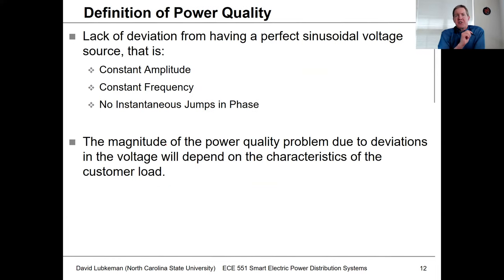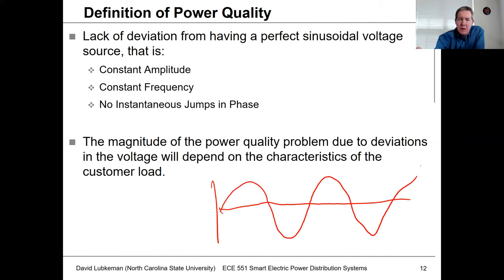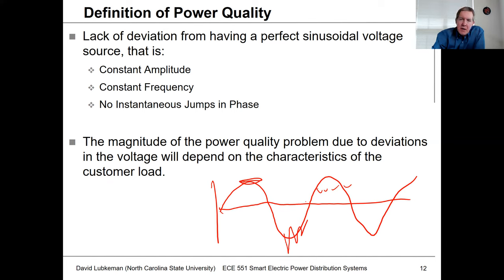The definition of power quality is any deviation from a constant-amplitude, constant-frequency voltage waveform. What the customer expects to see is a nice clean sine wave — constant amplitude, constant frequency, no instantaneous jumps in phase angle. But things can occur that cause the voltage to sag, cause ringing deviations. Any deviation from a pure 50 or 60 Hz waveform is a power quality issue.